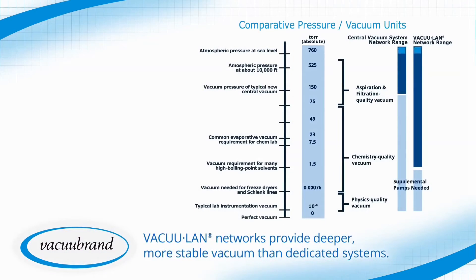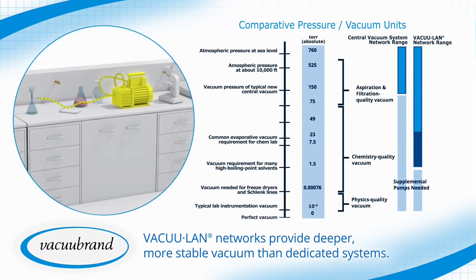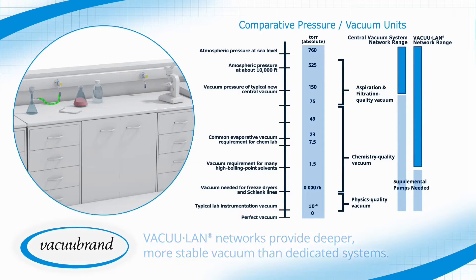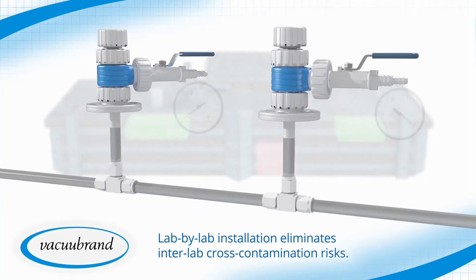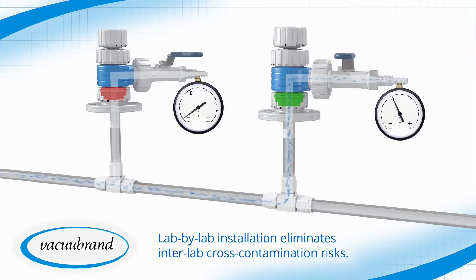VACUU·LAN networks provide deeper, more stable vacuum than central systems, reducing the need for space-wasting instrument-dedicated pumps. Lab-by-lab installation eliminates inter-lab cross-contamination risks, and the technology even mitigates cross-contamination risks within the lab through integrated check valves.